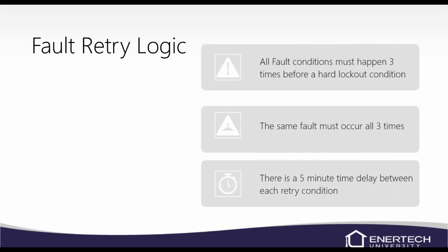So we have fault retry on this unit. If you have a high pressure lockout, the unit will shut down and it'll wait for 5 minutes and it'll try to restart. If that high pressure lockout happens 3 times, the unit will then go into what we call a hard lockout. The hard lockout will send a signal to the thermostat that says call for service, and then the unit will shut down and it will not try to restart.